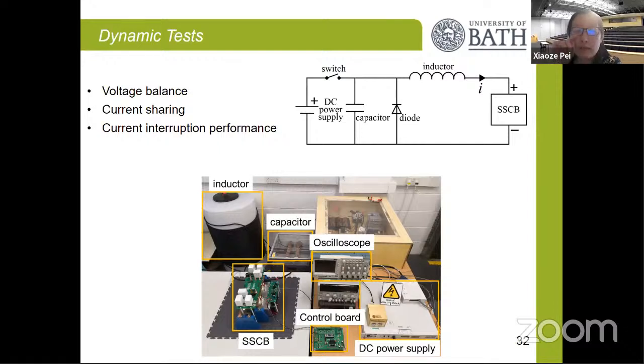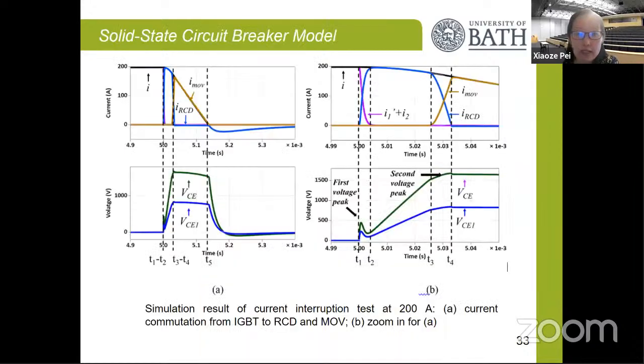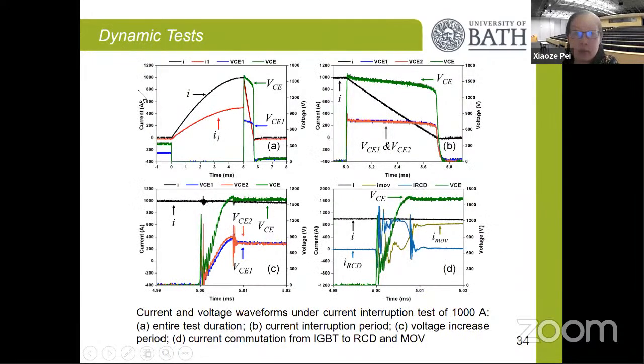And then we investigate the dynamic test, to see when there is a change of the current, does it still balance? So we did the simulation, and then we did the experimental result. We use a circuit to create a resonance current to simulate the fault current. So you can see this is the total fault current rising from 0 to 1,000 amps. And this is the total current in two parallel branches, and this is the current in one branch.